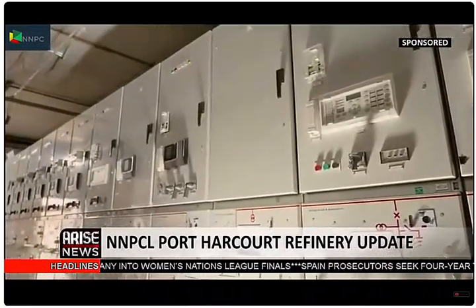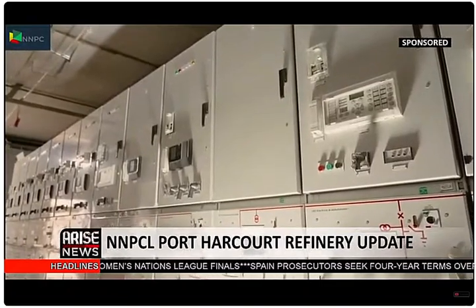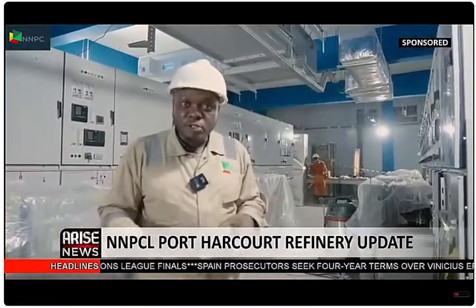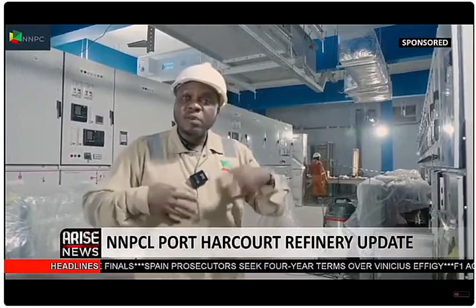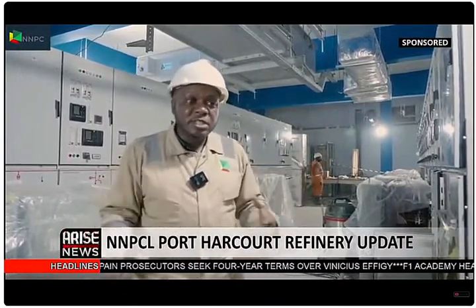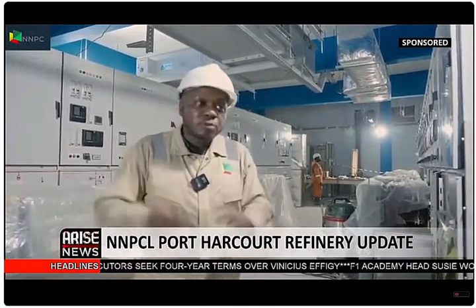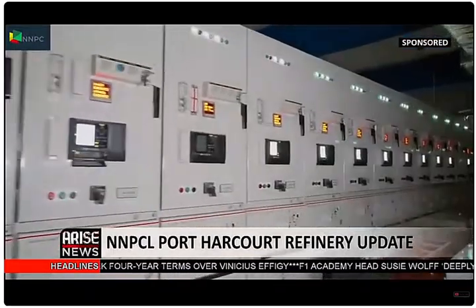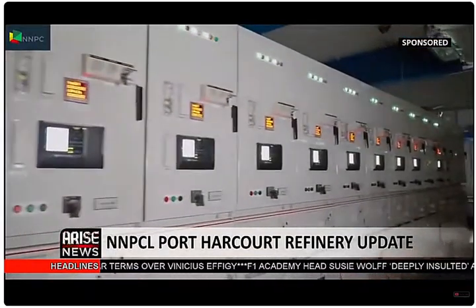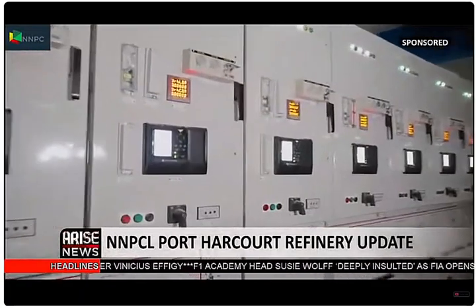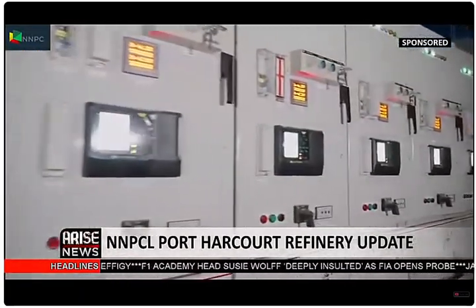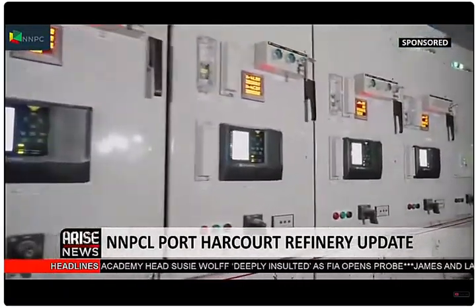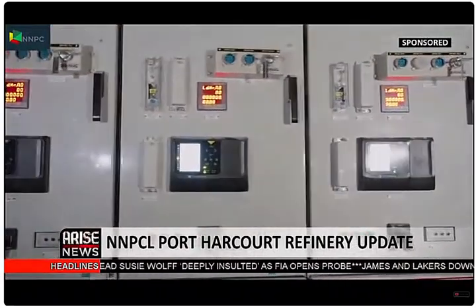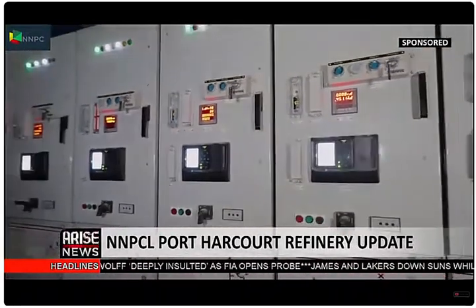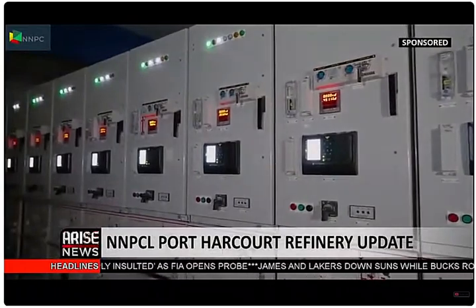It never comes down. It was a big contention even during design phase that took us close to 3 months to figure out. We, with the PHRC team, the PMC team, and the contractor had to come together and put our heads together. The substation, which contains high voltage panels, low voltage panels, and motor control center panels, receives 11,000 volts of electricity. From here, it is stepped down for distribution to other substations.